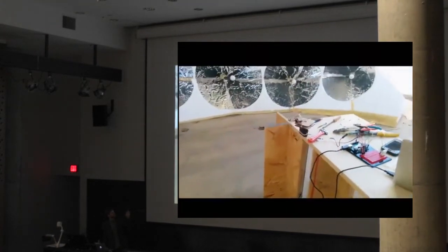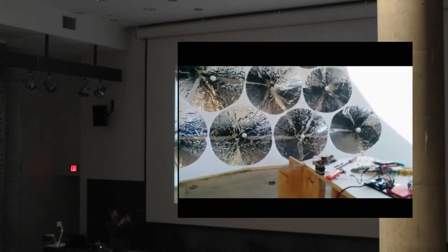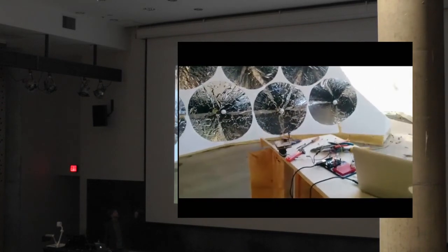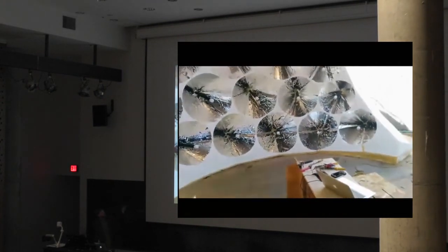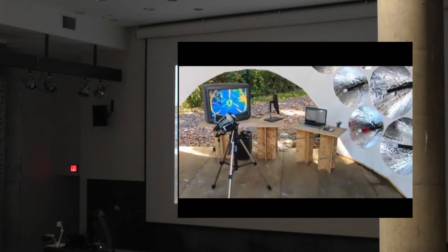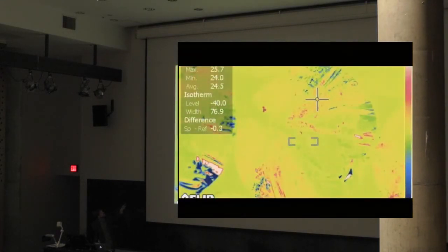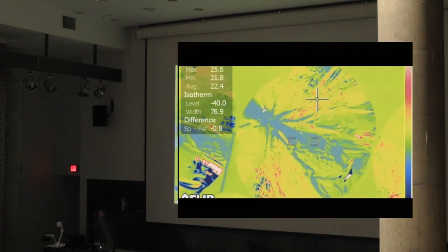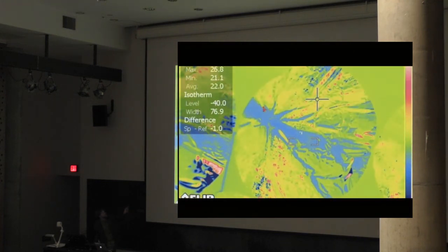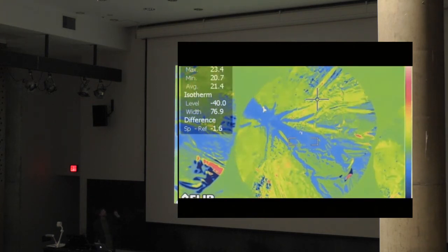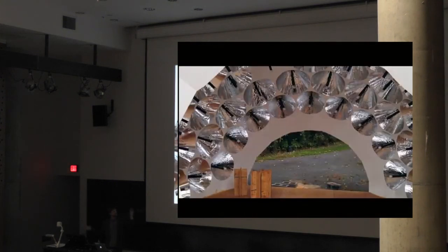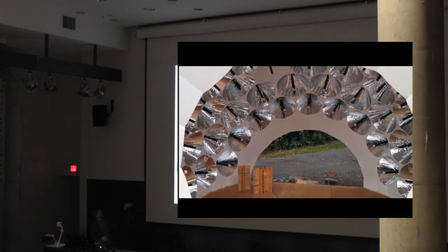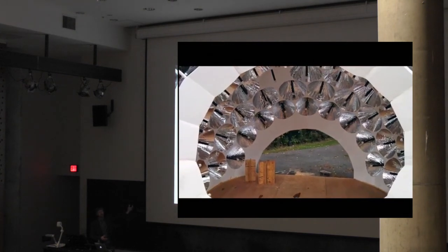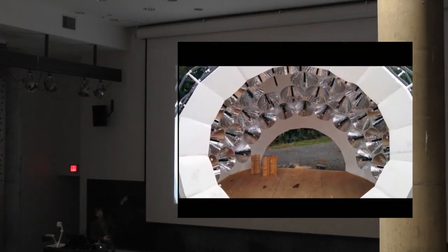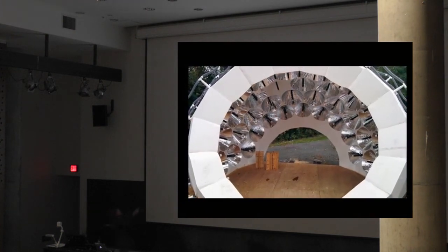Instead of just using one method, we also have a black globe thermometer that measures radiant temperature. One of the students built a little Arduino IR camera that spins around and records the radiant temperature, and you can see on the left how the temperatures change across the bolts. So you don't just see the bolt temperature, you see the temperature reflected out of the cones. This way we can calculate the virtual surface area you perceive in the system when sitting there, which is much larger than the actual surface area of the radiant black bolts or the cool water flowing through the system.